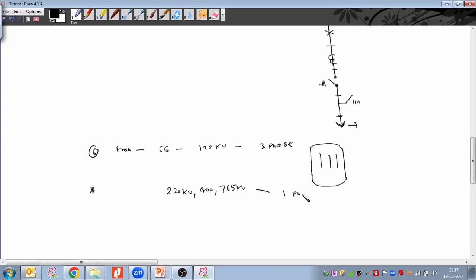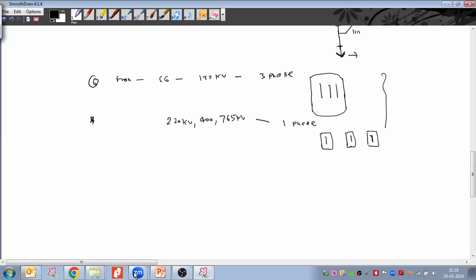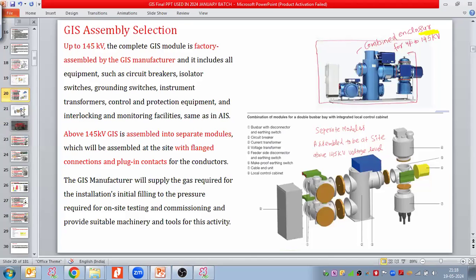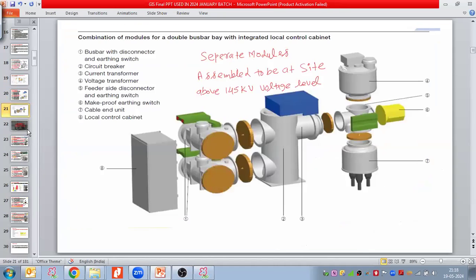single phase GIS, which means for R phase one separate module, for Y phase one separate module, for B phase one separate module, a phase-wise module, right? This is what we discussed yesterday, the phase segregation practice. When it is three phase, it is factory assembled, so it is assembled by the manufacturer. But when we are taking single phase, then it is to be assembled at the site with the help of flange and bolt connections. So that we have discussed yesterday.